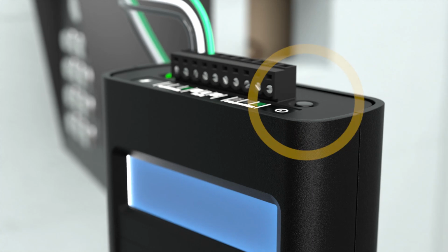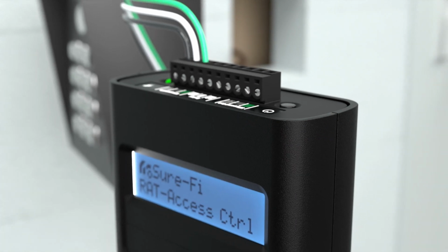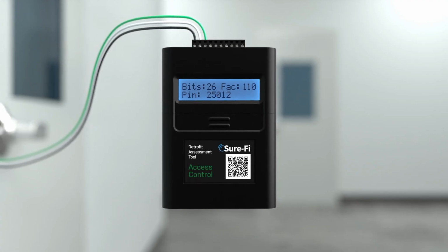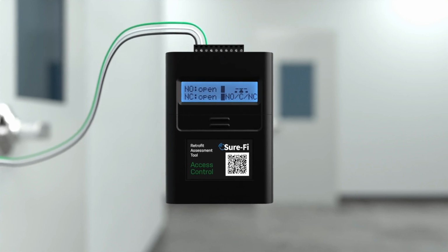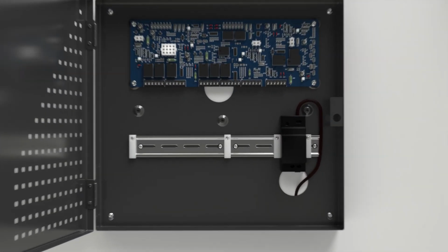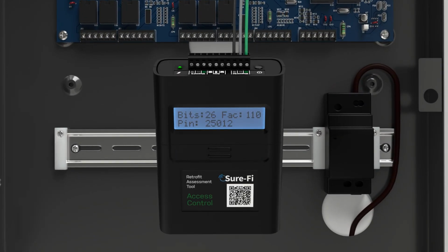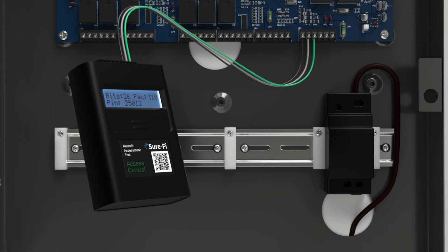Press the function button to cycle through the different displays on the tester to see the Wiegand values, line voltages, and relay status. To send Wiegand data, connect the output on the D0, D1, and ground on the assessment tool to your access control system.